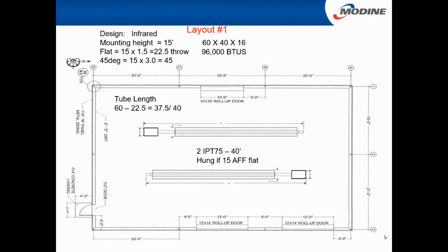The other thing, if you do 2 units and you do like we talked about, both burner boxes at the same end, if you want to common vent them, you certainly can. You can take the 2 4-inch and the 6-inch and out the roof. The only thing you have to do is make sure thermostats are tied together. Or one thermostat, I should say, because you're going to have one thermostat control both. If you have one come on and the other one tries to come on, it probably won't come on because it can't develop the pressure. But then you don't have that balance, like you said, with one burner box down here and one down here. Yeah, you wouldn't have the balance either. But still a good application.